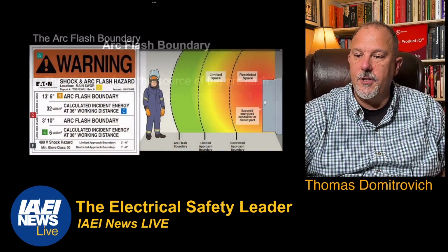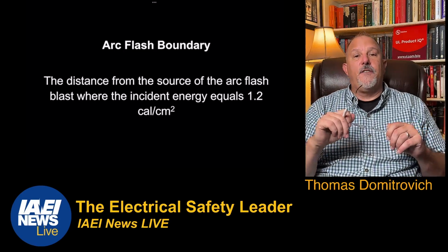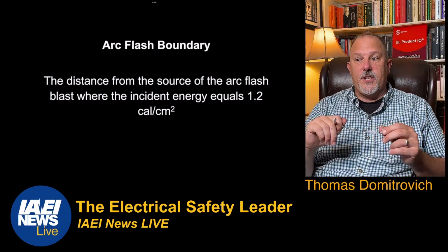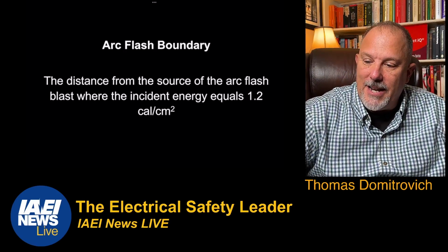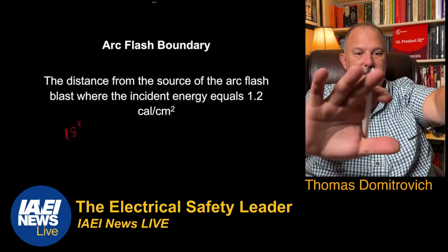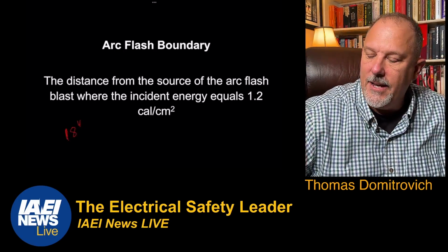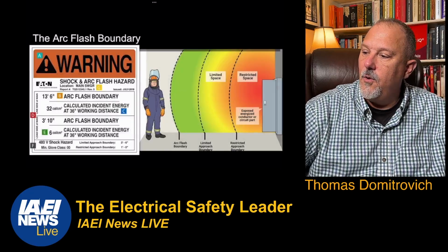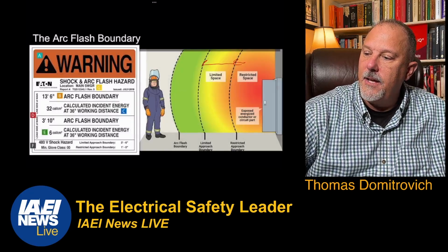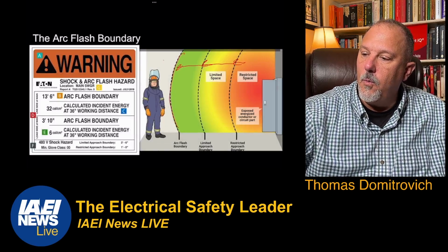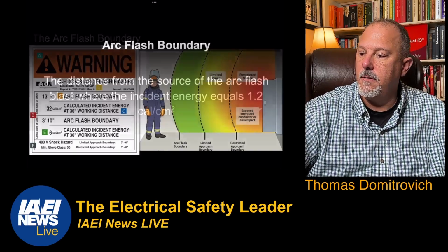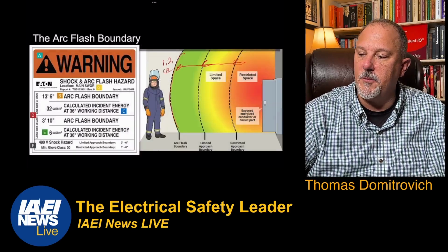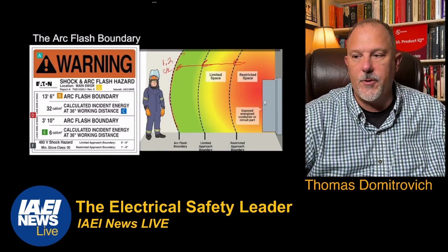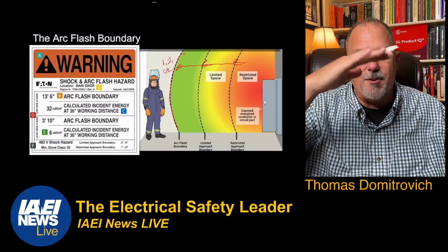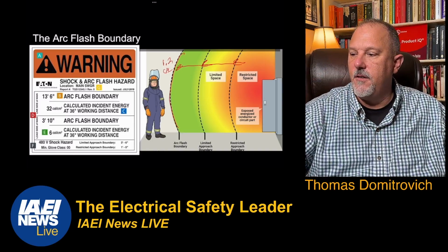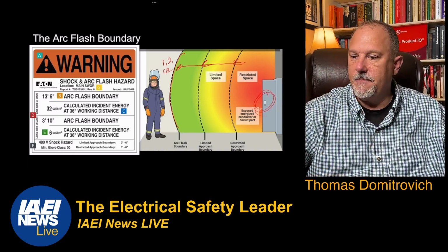And you have your barriers, you know that, arc flash boundaries, that's the distance. Your arc flash boundary, that we want to get to 1.2 calories per centimeter squared. So what we do is we calculate what, at 18 inches? That's your working distance, that's hands to chest, okay? 18 inches. And then we keep going back until we hit a number of 1.2 calories per centimeter squared, and that's where we establish our arc flash boundary. After that point, the further away you get from the arc, from the event, the lower the energy is.